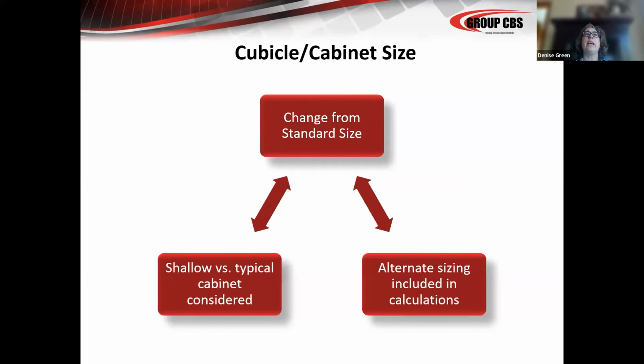So it's too hard to model for every single different kind of circuit breaker. The formulas, if you've ever looked at the formulas for calculating available incident energy, it's back to calculus and all of that. And to add a different coefficient for an AK25 versus a DS416 versus a K1600, they just can't add all of those volumetric calculations. It was hard enough to come up with different sizing components away from the 20 by 20 by 20. So it takes into account the volume of the cell, if that helps. Yep, thank you.